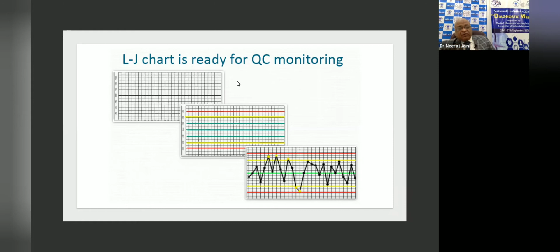If one value is beyond 3 standard deviations, that means it is significantly away from the rest of the data. Stop testing. Do the root cause analysis. What has happened? Why is it away? Take appropriate action, run control again. When that control result is within acceptable limits, only then run patient samples. If one value is beyond 2 standard deviations, you can accept this once, but carefully watch the next run. If that is again beyond 2 standard deviations, that means something has happened which has started affecting all our results. Stop testing. Do the root cause analysis, take appropriate action, after that run control again, and then run patient samples.